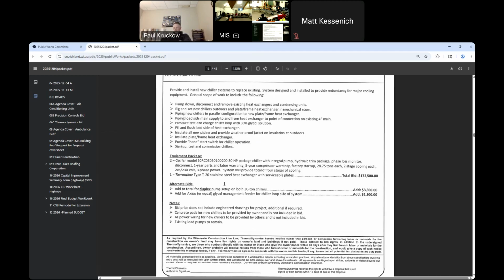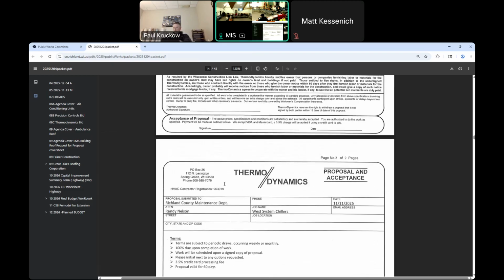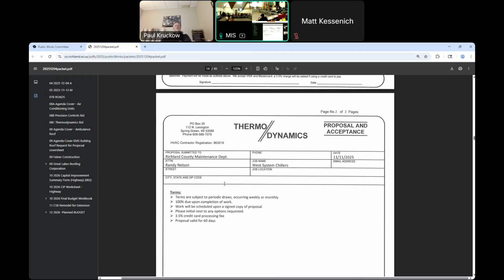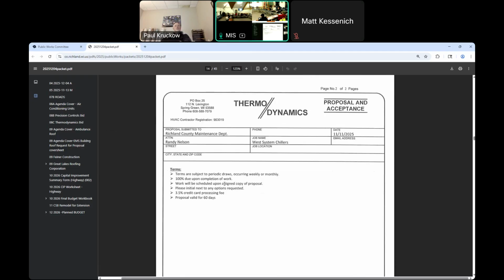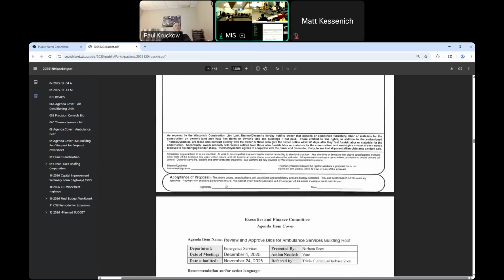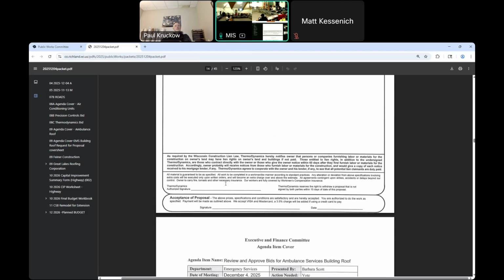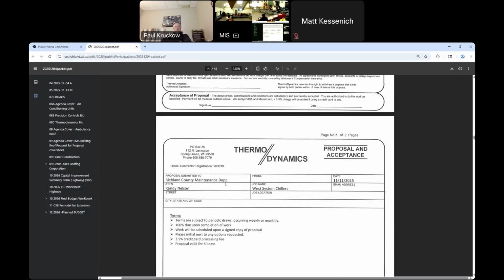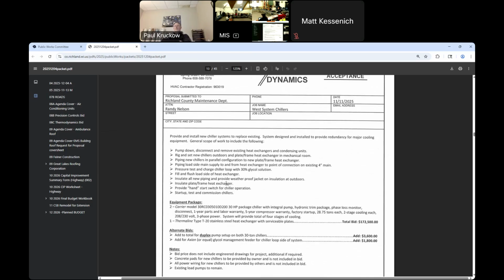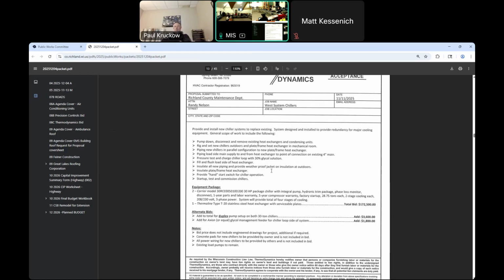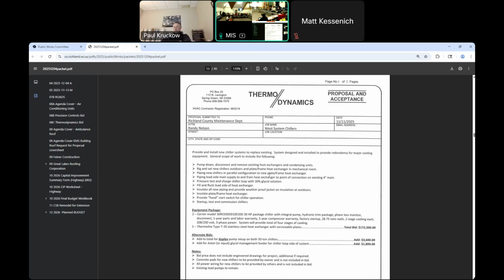Another concern, a side issue to this that I think you might want to address: your load pumps in the building aren't redundant, and in this project you're not replacing load pumps. I looked at them while I was here and they're pretty old pumps. You could have all the nice chiller setup you want outdoors, but if your load pump goes down, that air handler is done. So you really need to consider that. We didn't put any kind of proposal together on those load pumps, but it is a consideration.